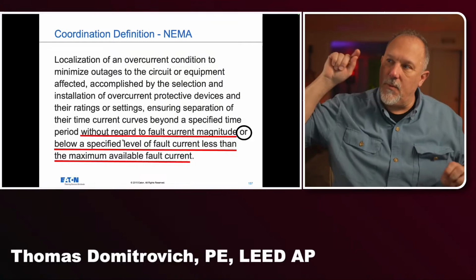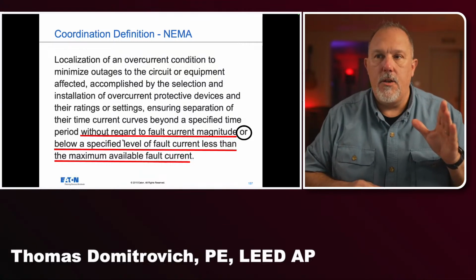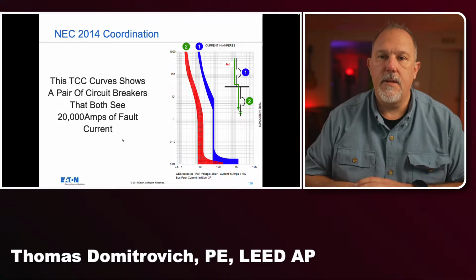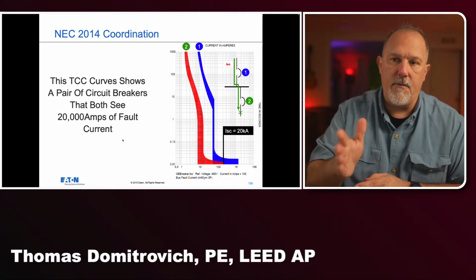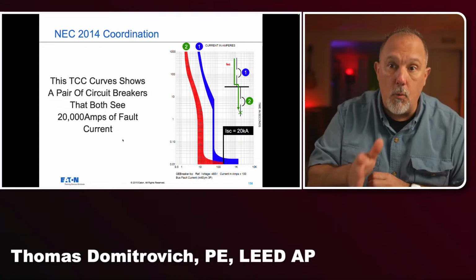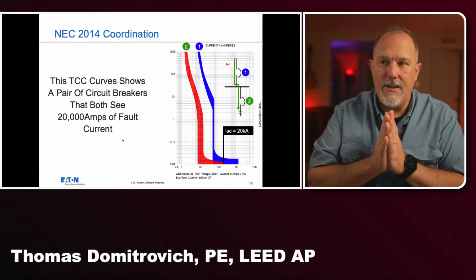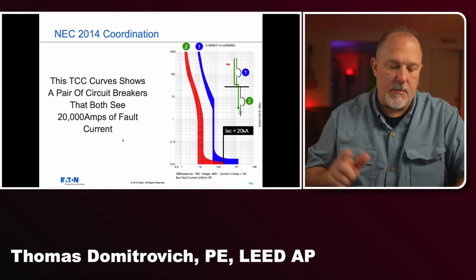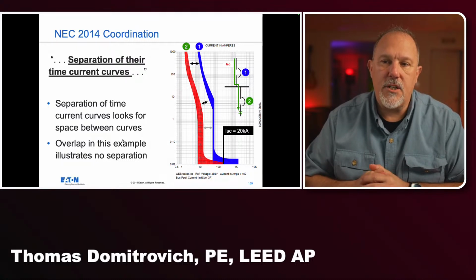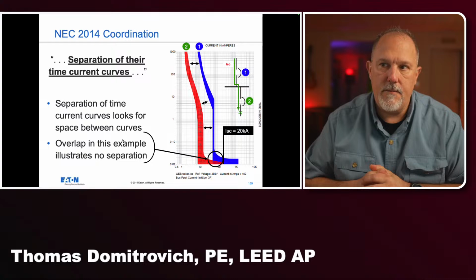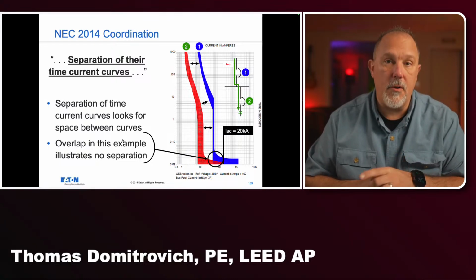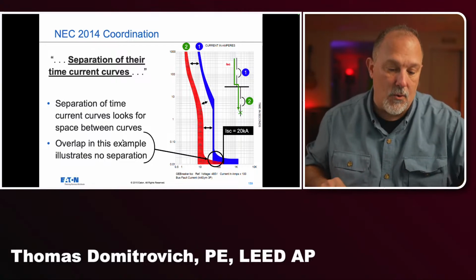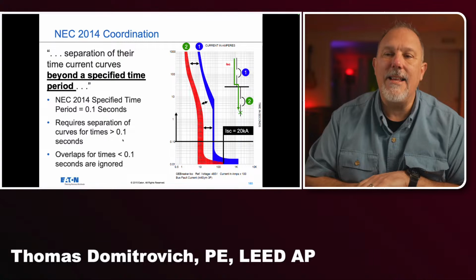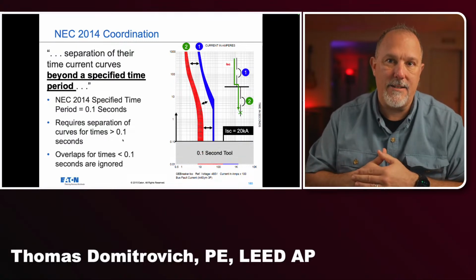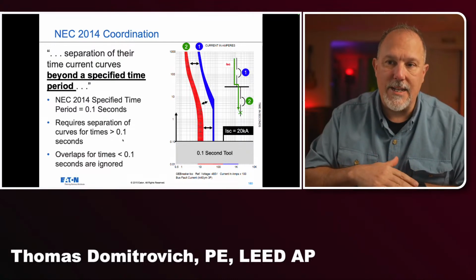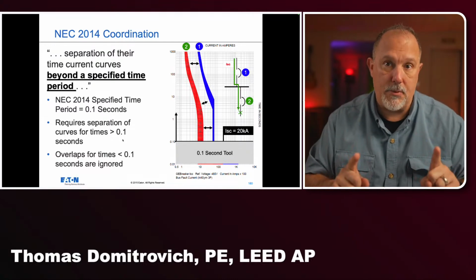And I made sure we had the 'or below,' because let's just do this. Let's say that I have these two, and I know I have available fault current of 20,000 amps, and I know they're both going to open. I've got a few things to address when this is a problem. I have to have separation of trip curves, but I have an overlap. I tell people, if you're going to do 0.1 seconds, you need the handy dandy 0.1 second tool. And what do we use? We basically hide everything below 0.1 seconds. Once you hide everything below 0.1 seconds, the problem goes away from an overlap perspective.